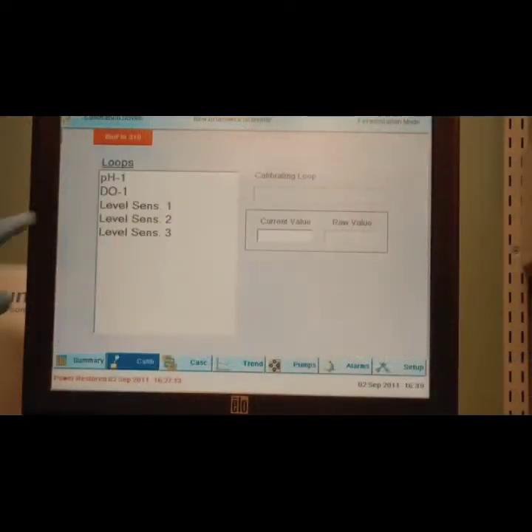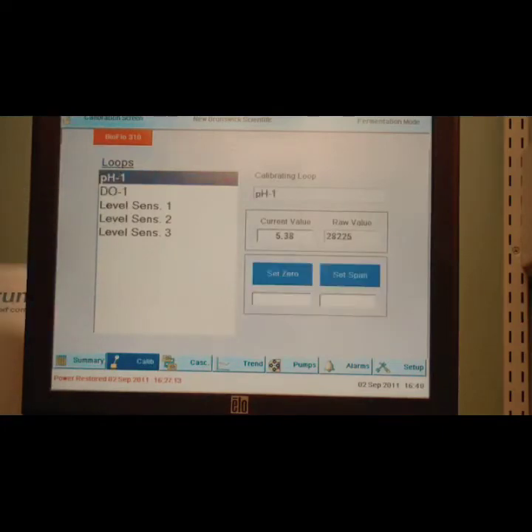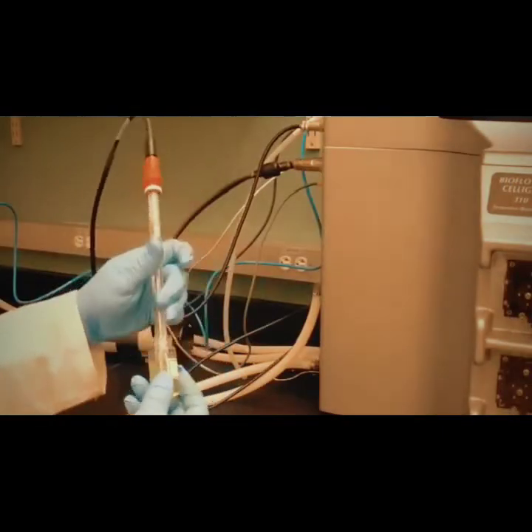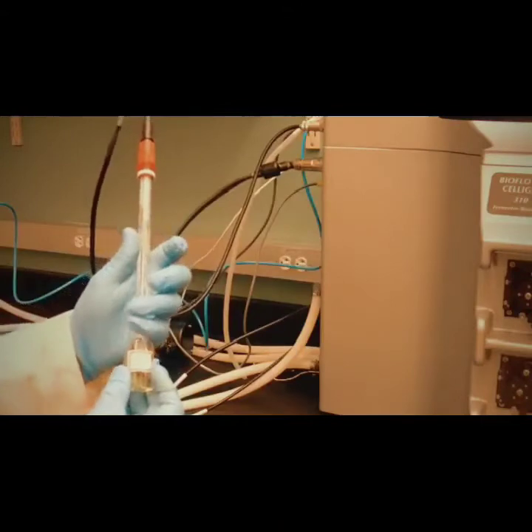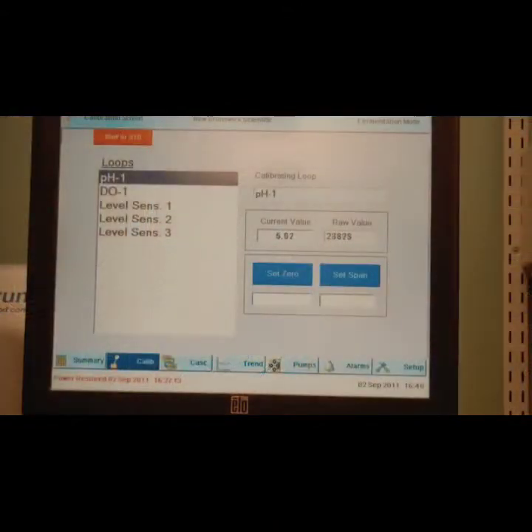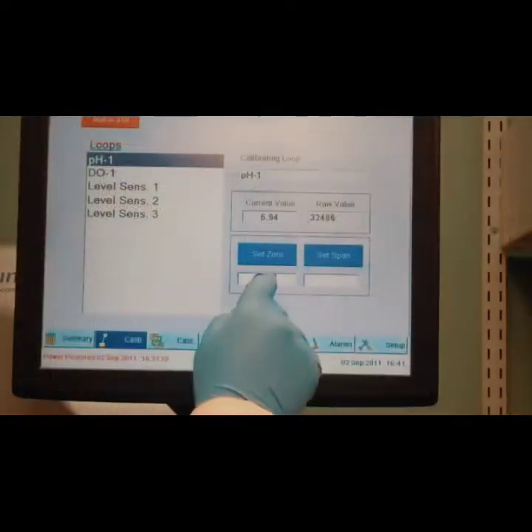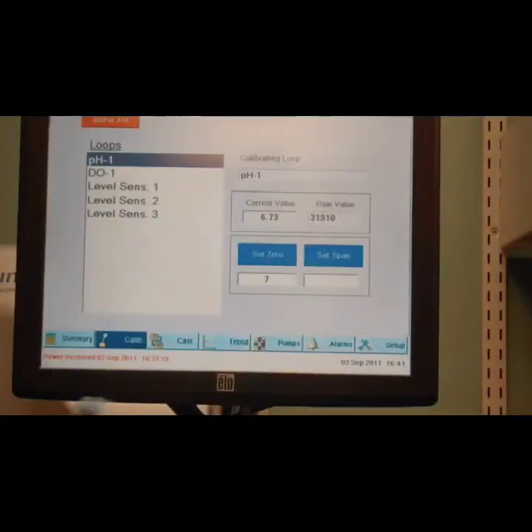On the PCU, select the Calibrate button and then pH probe. Immerse the pH probe in 7 buffer and allow the raw input signal to stabilize. Enter the value 7 in the box below the Set 0 button and press Enter. Press the Set 0 button to accept the value. Repeat the pH calibration process to set the span using a 4 buffer solution.